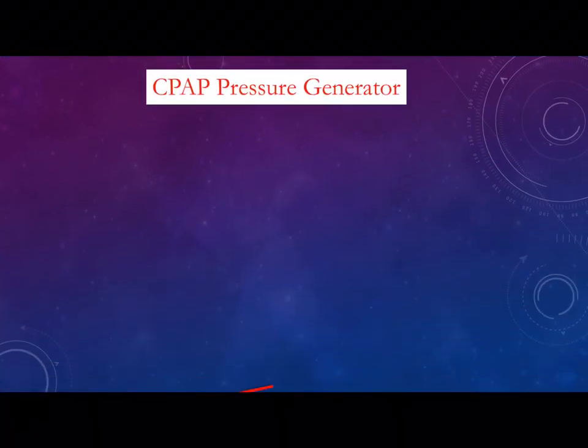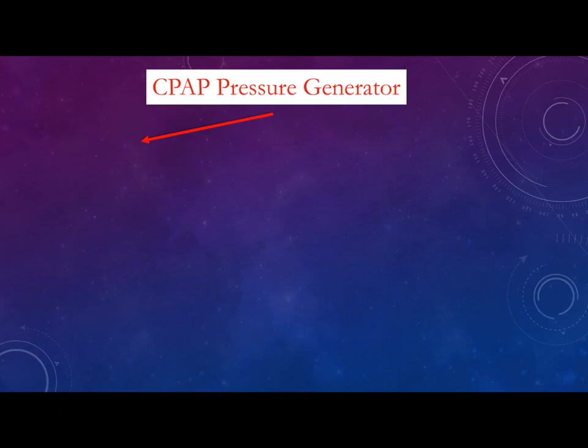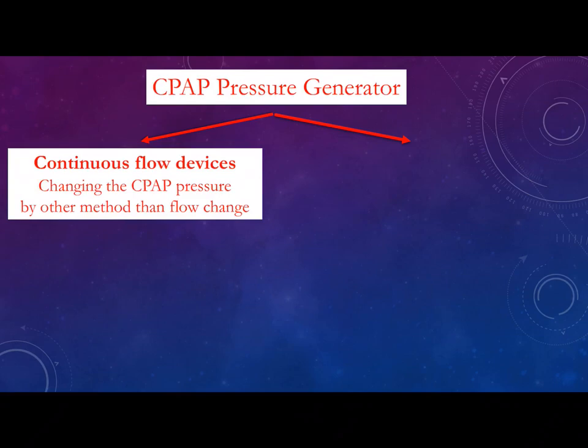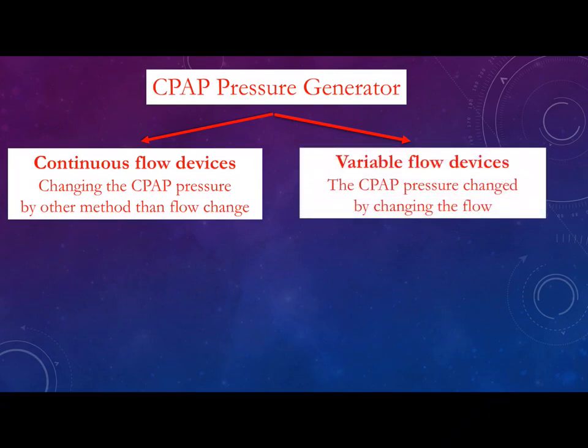The second component is the CPAP pressure generator. According to the method of pressure generation, we have two types of CPAP: continuous flow devices and variable flow devices. In continuous flow, we change the pressure by methods other than flow, so increasing or decreasing flow mostly does not affect the pressure, which remains fixed. In variable flow devices, the CPAP pressure changes by changing the flow — increasing flow increases pressure, and decreasing flow decreases pressure.